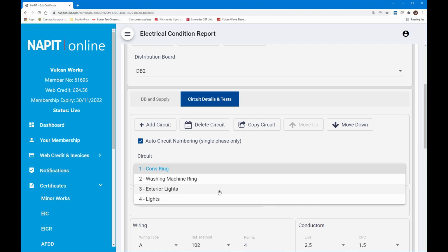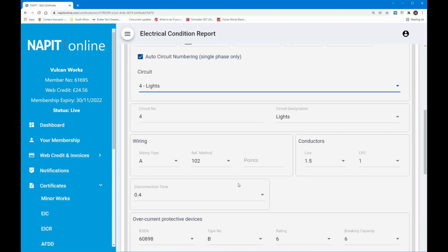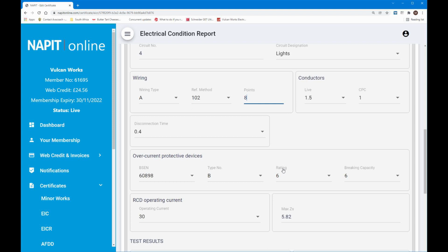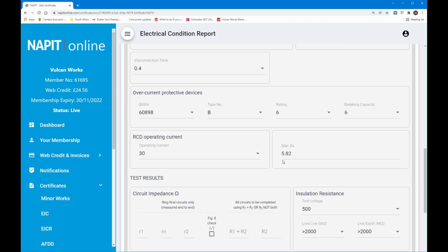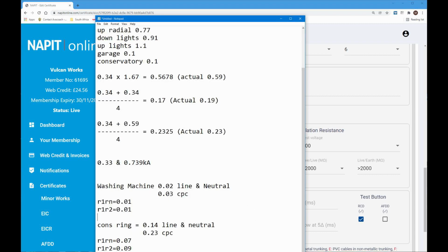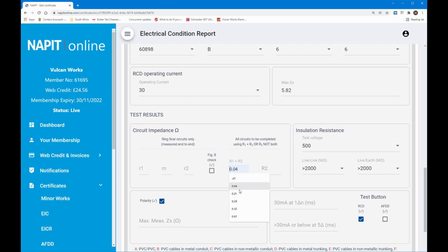Now the exterior light has since been replaced, and when I go back to do the remedial work, I will be able to do the proper readings for that, and they will go in the new EICR, which will pass. So we're leaving the exterior lights on this one, and we're going to do the normal interior lights. There were quite a few lights on this, as you probably saw. A lot of spotlights. I think there are 8 in total, if I remember correctly. Again, 1.5, and all the reference methods are there. And again, 6 amp rating, a 5.82 maximum ZS. This isn't a ring. The reading for the interior lights was 0.53. Add that to the ZE, which was 0.33, gives a reading of 0.86.